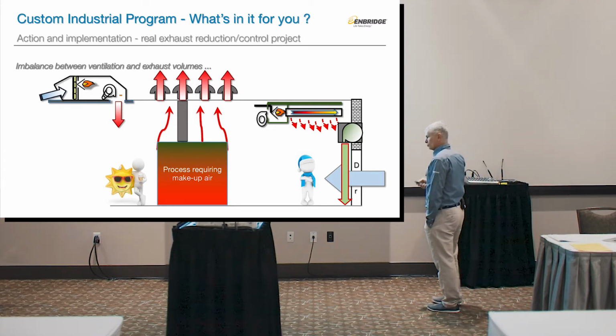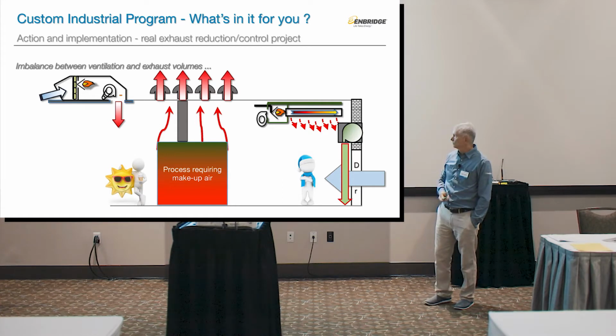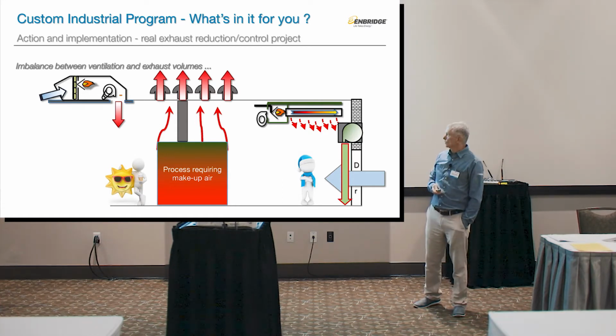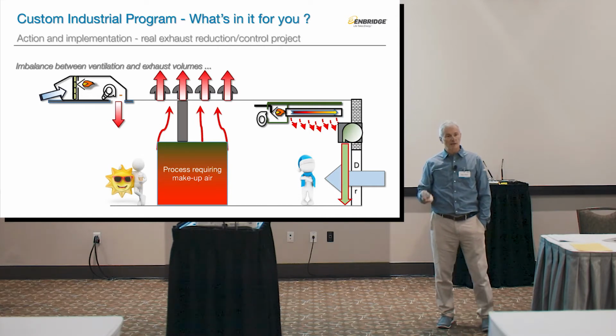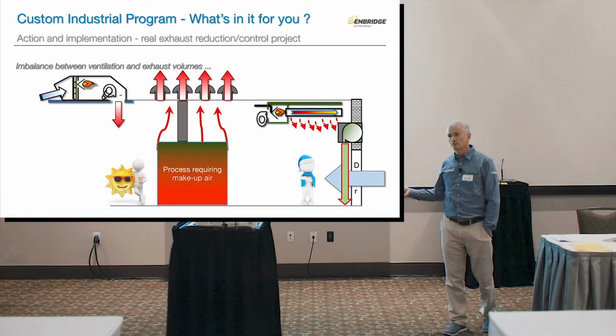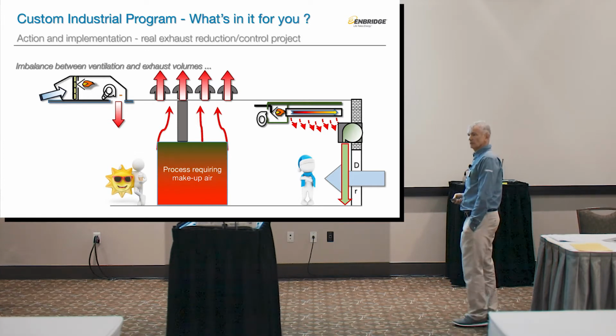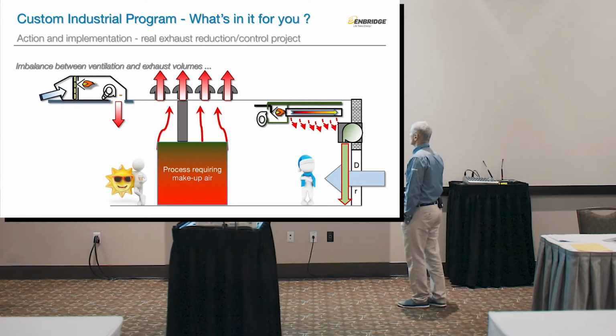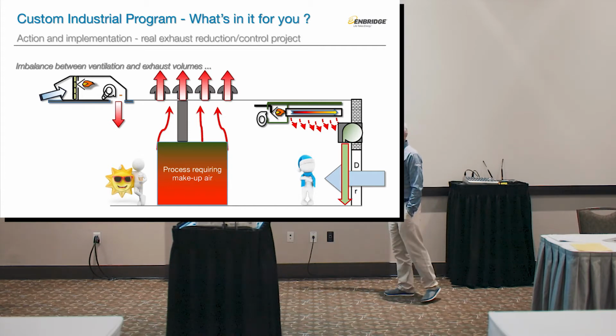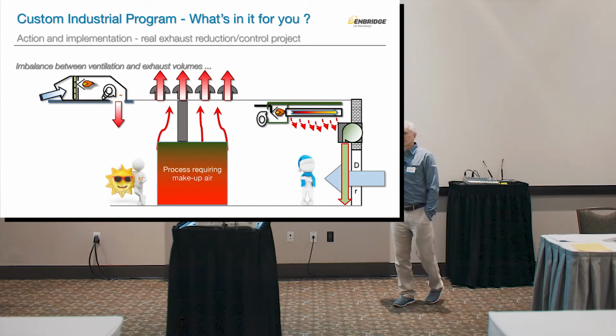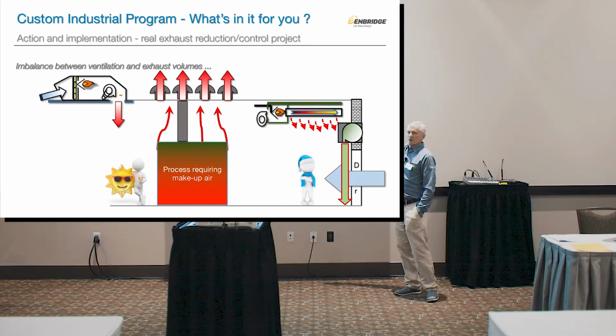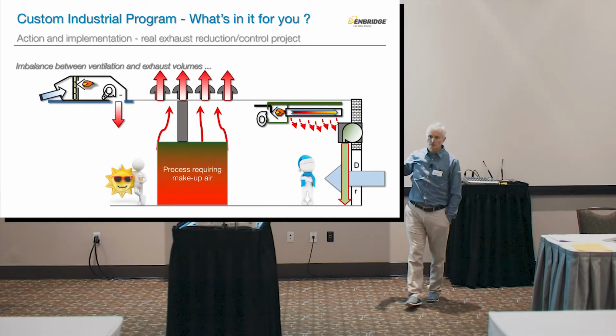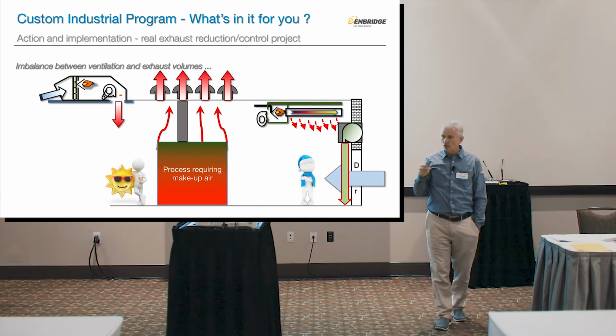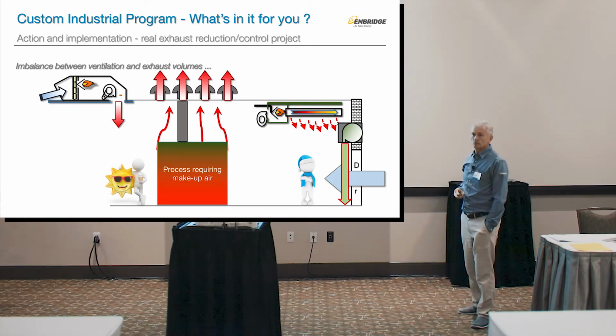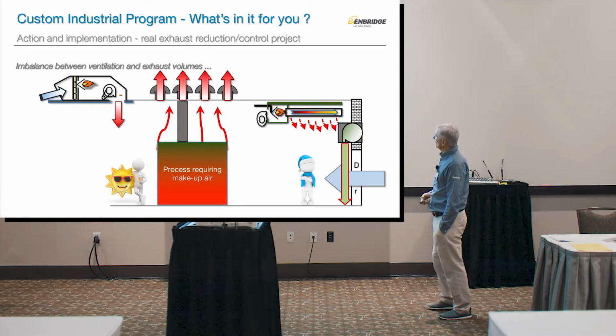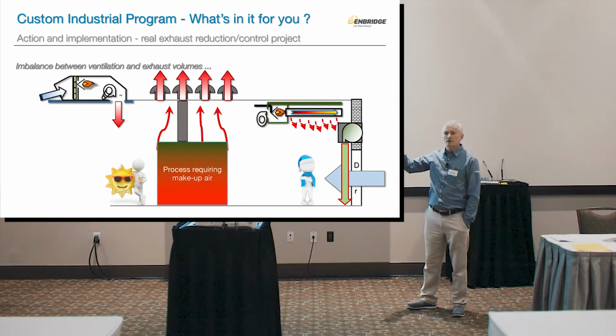So plant managers, to do it fast, efficient, and effective, drill a couple of holes and put exhaust on top, which is a valid solution. I would do the same. Problem is, those are not tied to anything. So when the winter comes, you have all this air pulling through the facility by that imbalance. So you have this guy freezing, and then we have people installing infrared heaters or air curtains, all sorts of stuff that doesn't work. As long as you have that much imbalance, they do not work. And what would happen is a cold, drafty space.